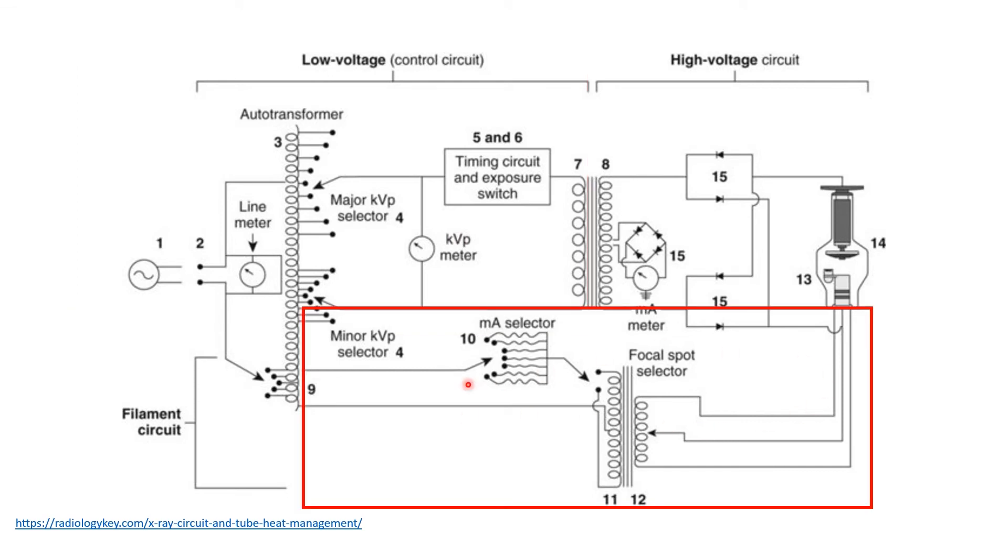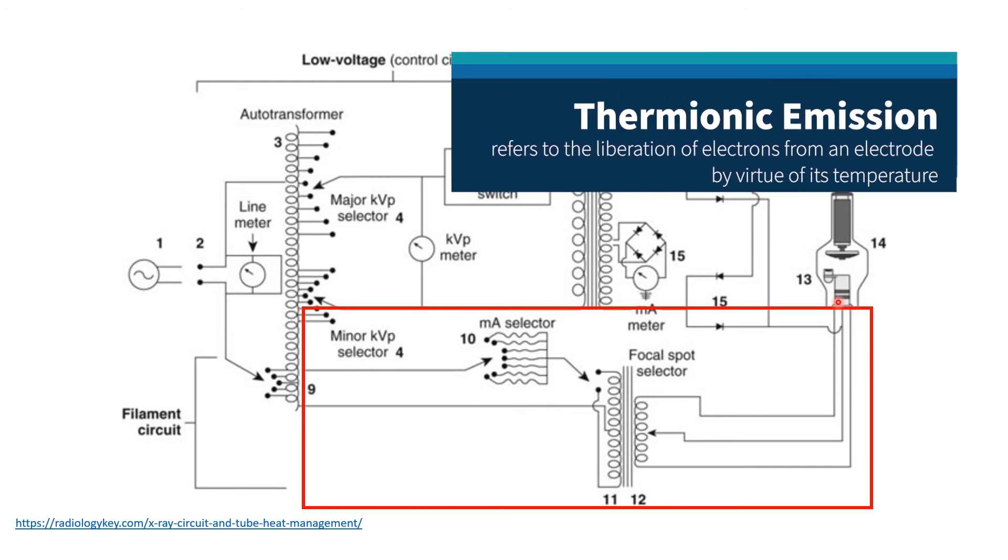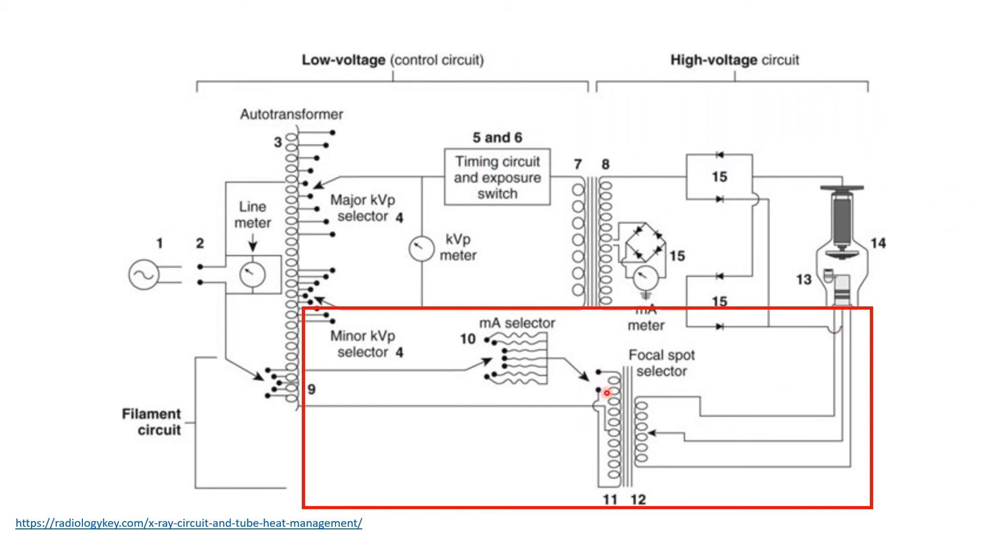Next, we have the filament circuit. This is a sub-circuit that supplies low current to induce thermionic emission of electrons at the filament side of our X-ray tube. We have here a step-down transformer before introducing the current to the filament. This circuit is activated by the operator through the adjustment of the MA.